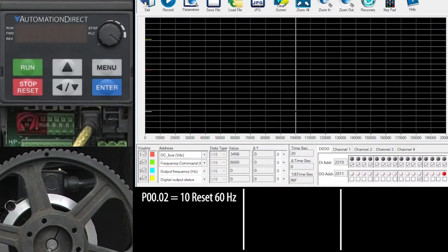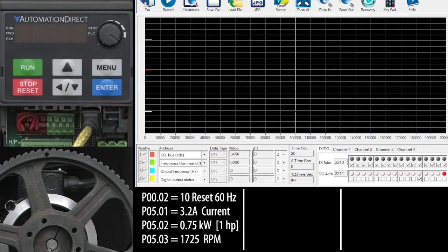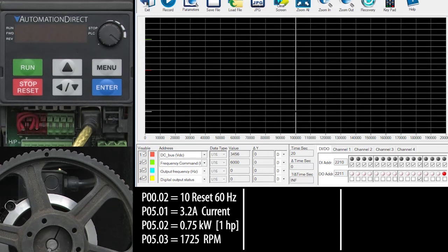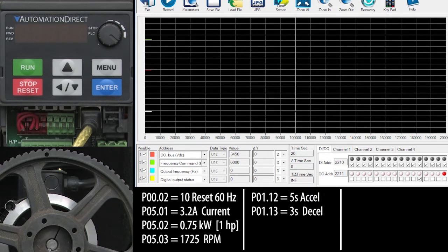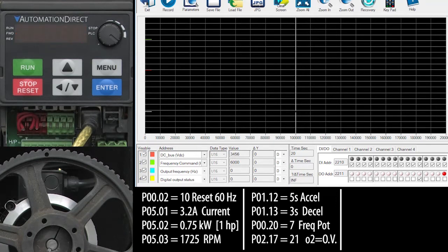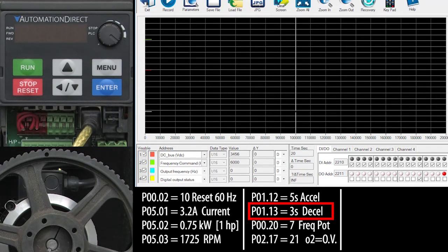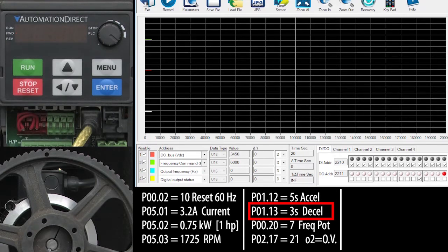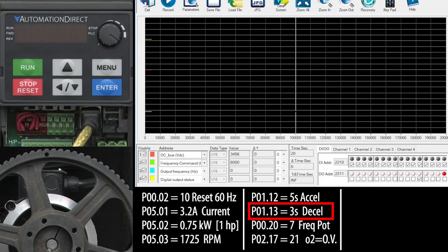I reset the drive to factory default so you know exactly where I'm starting from and then I set up the drive with my motor parameters and these ramp rates. I also enabled the frequency potentiometer on the keypad and I'm sending the drives internal overvoltage signal to output 2. Notice that the deceleration time is set at 3 seconds. That's not really reasonable for this large pulley's mass, but will make for a good first test for us.